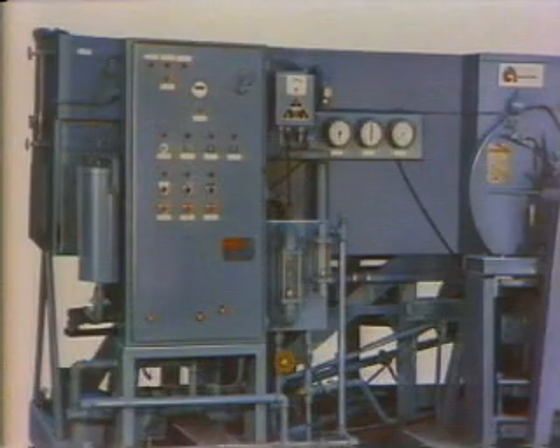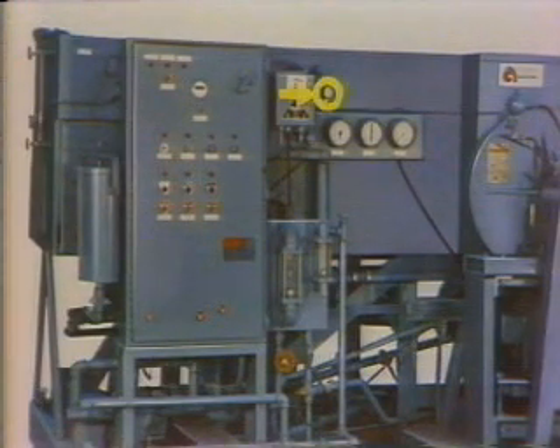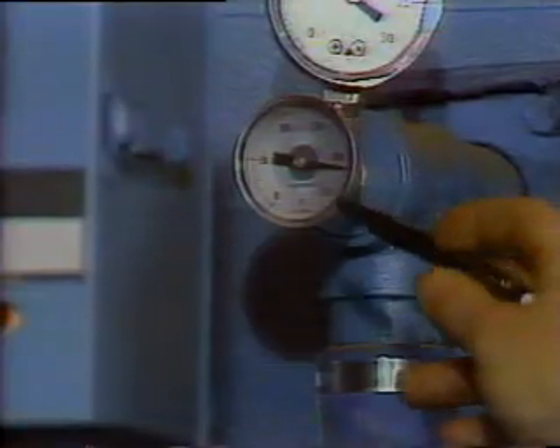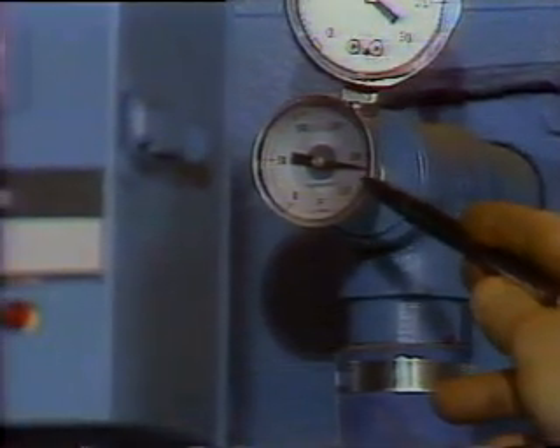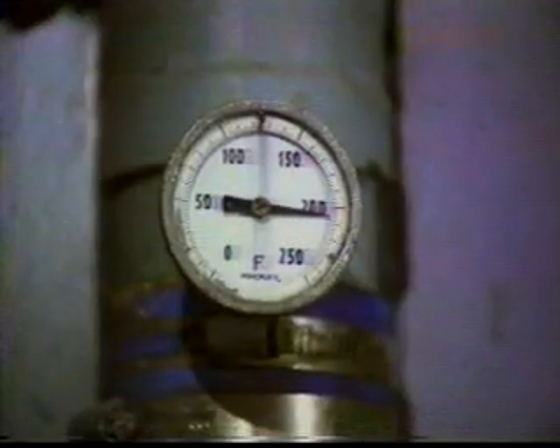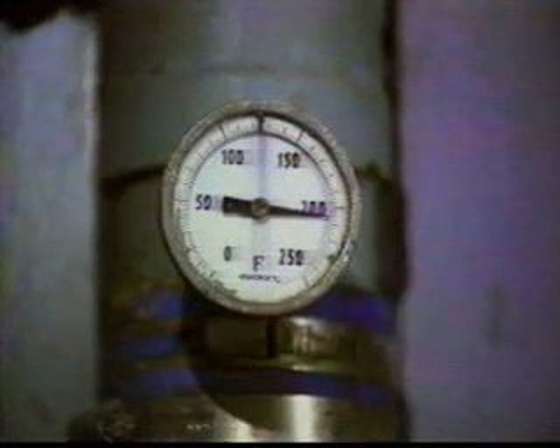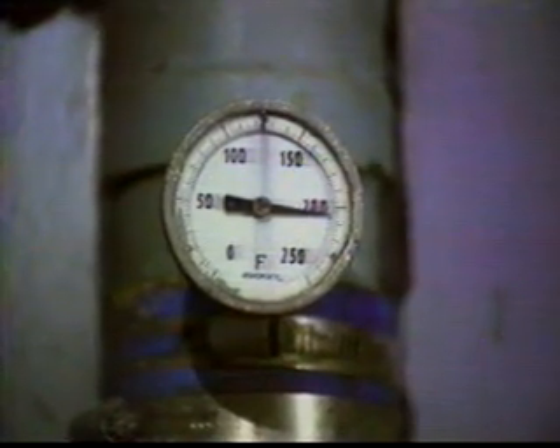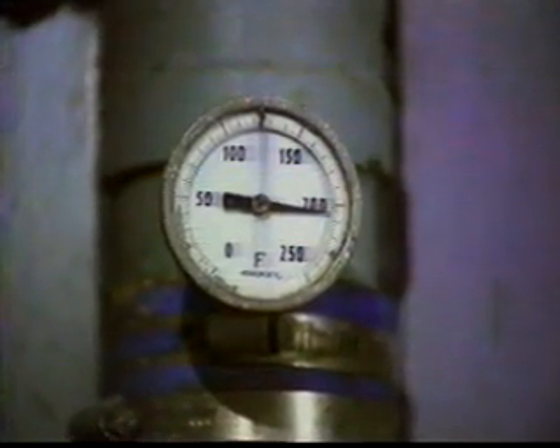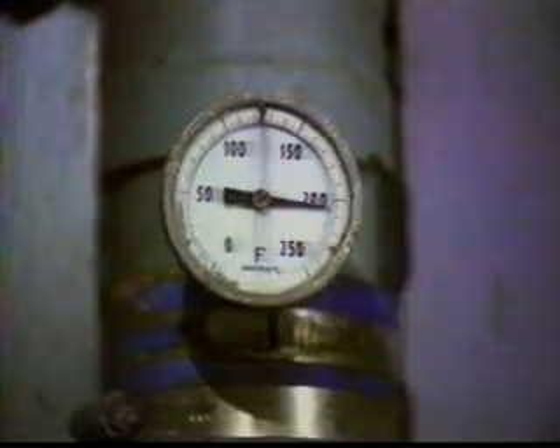Next, check the recirculation temperature, located here. It should read about 214 degrees. As the temperature gets higher, it raises the pressure of the evaporator. It'll shut the unit down at 2 psig. Too low a temperature will cause the pressure to drop, and the unit will shut off at below 0.5 inches of mercury vacuum. We've already talked about the remedy for this.